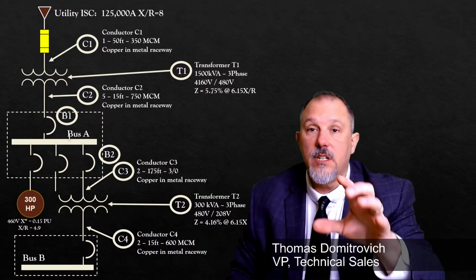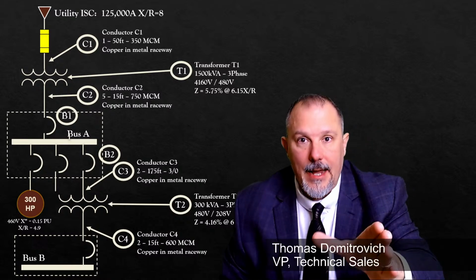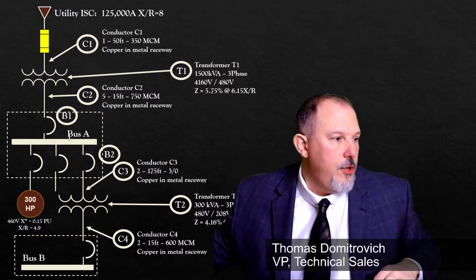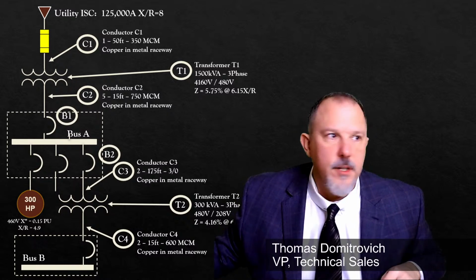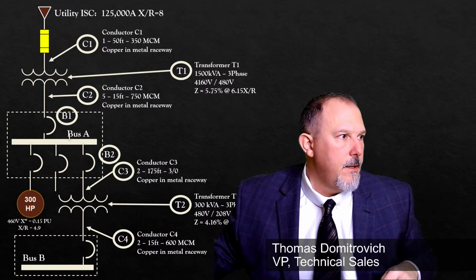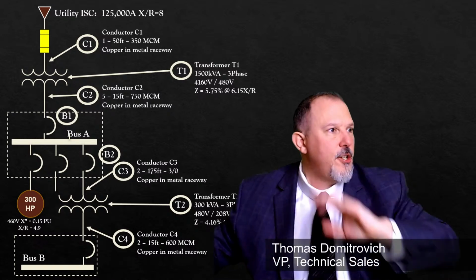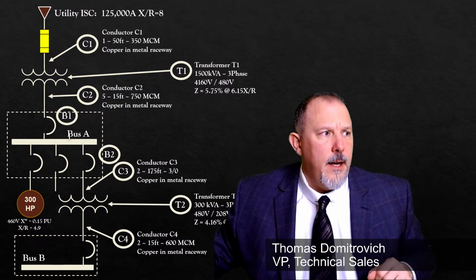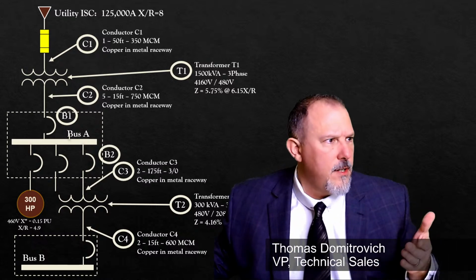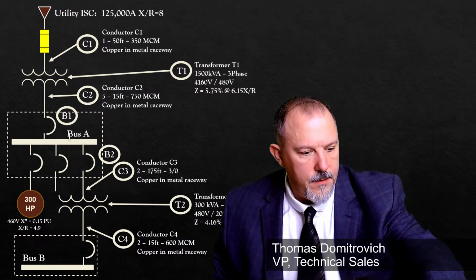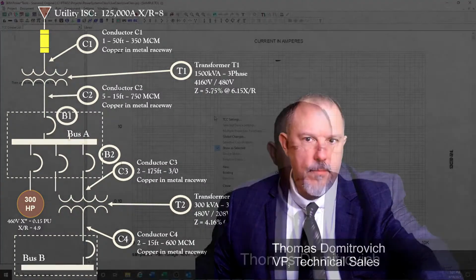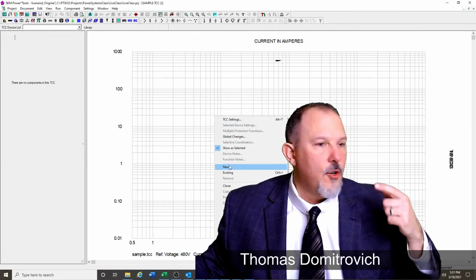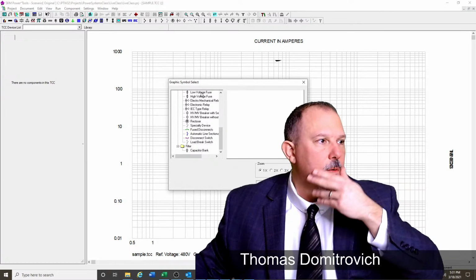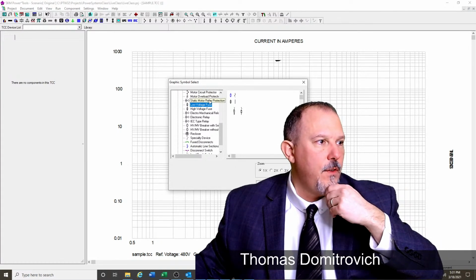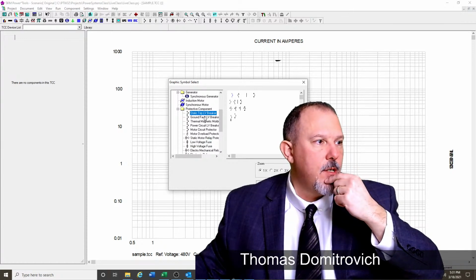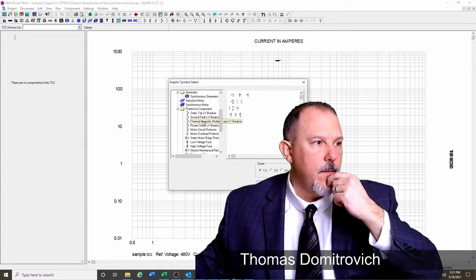With circuit breakers especially, my delay, if I showed you two trip curves, I'm just going to create a TCC curve here. I'm going to call this sample, and I know I'm not showing this right now, but bear with me. Patience. I hear you yelling. So, me with monitor 1, I'm going to create a new one. I'm going to create a low voltage, not a fuse, because we're going to talk fuses. I'm going to do a thermomagnetic circuit breaker, molded case circuit breaker.